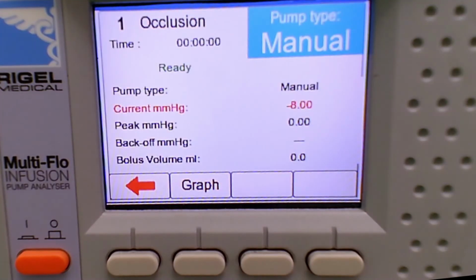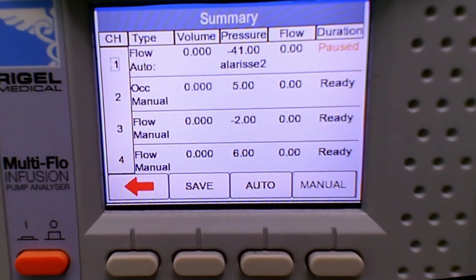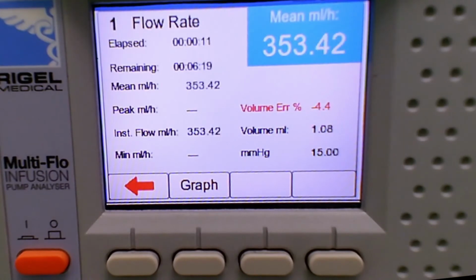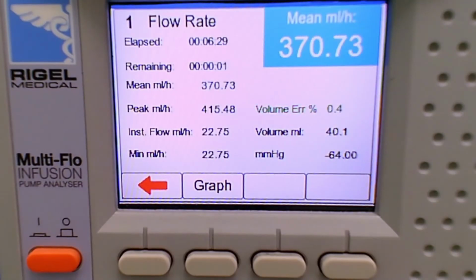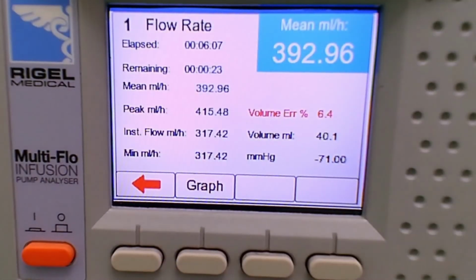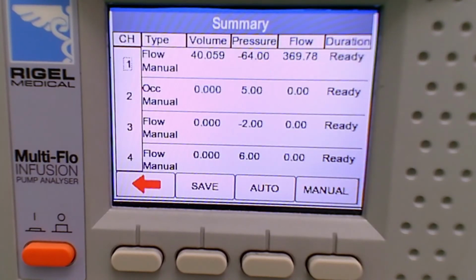So if we skip quickly through the tests, we've got flow rate done. We'll go to occlusion. We won't actually do the occlusion test, we'll just end that and go through to the next flow rate test. We'll run through for the 40 ml infusion to be infused, and then we can wait for that test to complete. We've already got the volume is complete, but we'll just wait for the time to elapse. So that's all the 3 tests done, except we've skipped the occlusion, and that's now saved and complete. We've got to click save, which is the second function button, and then we can go and access the results under that asset ID name. So it's really easy to set up an automatic test with a Multi-Flo.